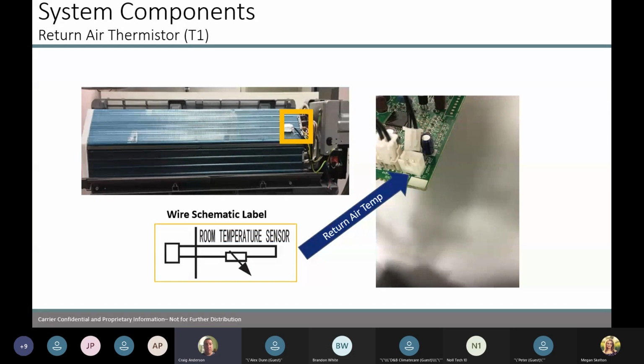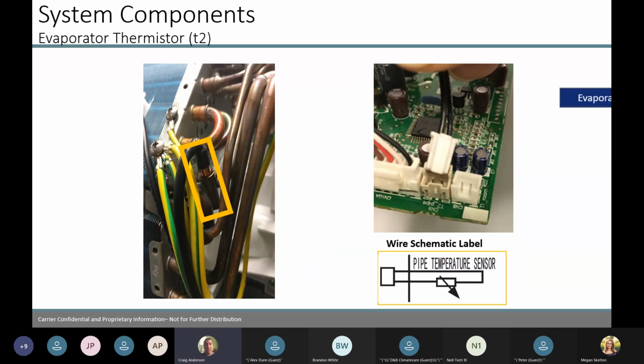So that is mounted on the inside of the coil. Once you take the cover off, just make sure it's in place and it's reading everything properly. It just plugs into the board and goes right to that coil. Evaporator thermistor, it plugs into the board as well beside the other one. You can't mix match them. They're different, so we can't plug one into the other.